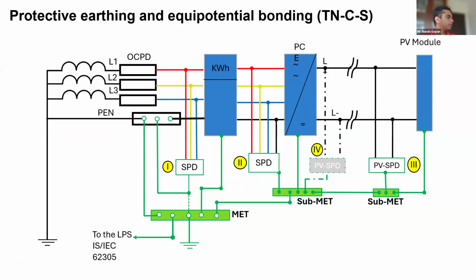So in a prosumer installation, and in any installation, you are supposed to have an MET, and the MET should be connected to all the exposed and extraneous conductive parts. This will be the body of the inverter, the body of the PV module, and all the other metal parts. You are supposed to connect them to the MET, and from the MET it should also be connected to the lightning protection. So this is how the earthing should be done.